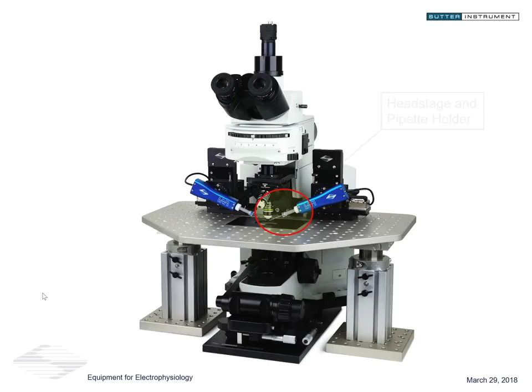Yeah, the dielectric properties of quartz, if you use it for pipettes, make the recording quieter. And of course, we were hoping that making the pipette holder out of quartz, the barrel out of quartz, would also make a difference. Unfortunately, we have not been able to detect any significant differences in noise performance between the polycarbonate barrels and the quartz barrels. As much as I would love to say they're quieter, it does not look like it. They're definitely not more noisy. It kind of makes sense since the quartz is not in touch with the electrolyte, with the pipette solution directly, or with the bath solution for that matter. So it kind of makes sense that the impact on the noise performance is a little smaller than with the pipette material.